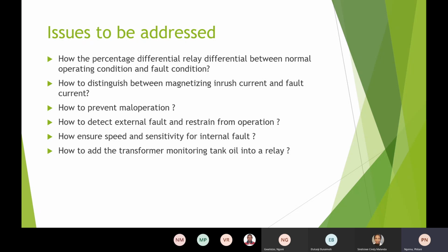And one of the issues that I want to address in this research is transformer oil monitoring. As much as we have the Buchholz relay on that one, I believe that we should have another protection of the oil in a transformer. The relay itself has to have a way of seeing the oil level and indicating whether the oil is in a good state and not hot, as the oil is for the insulation and also the cooling of the transformer.